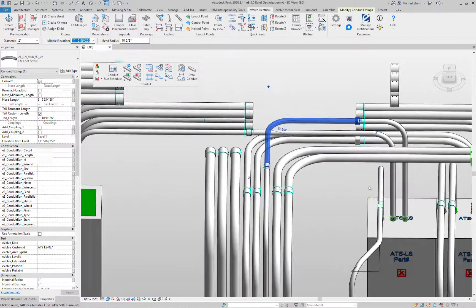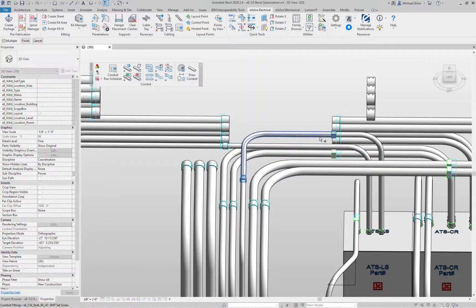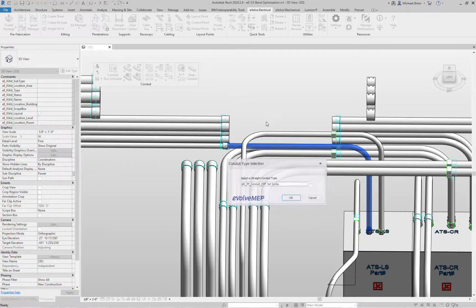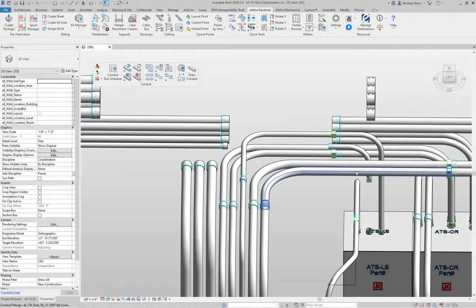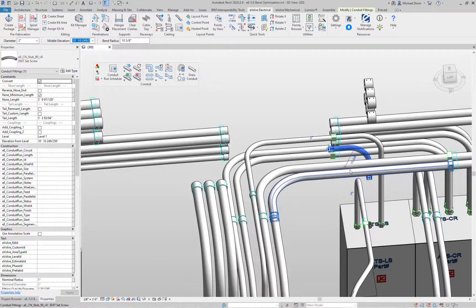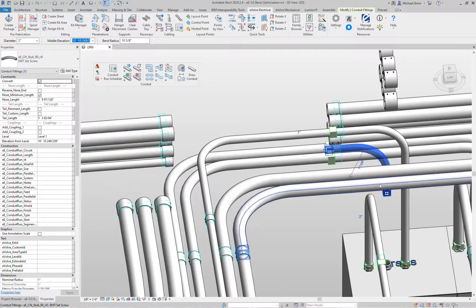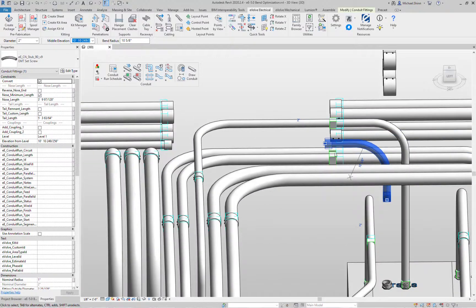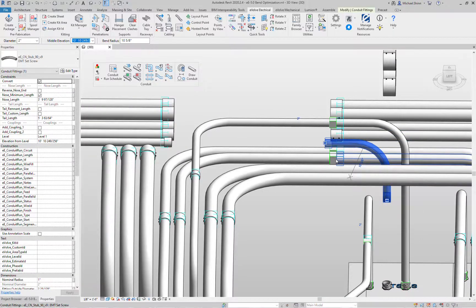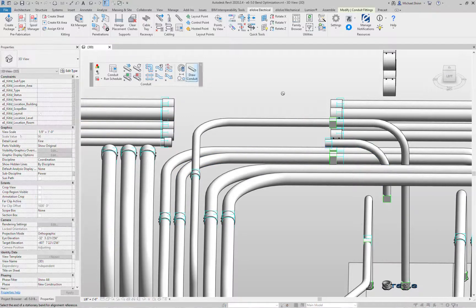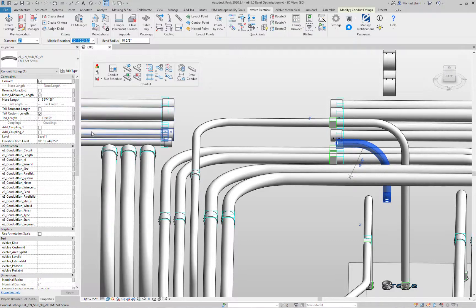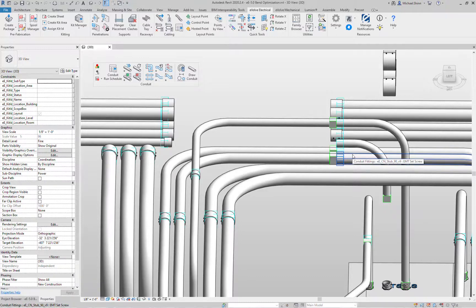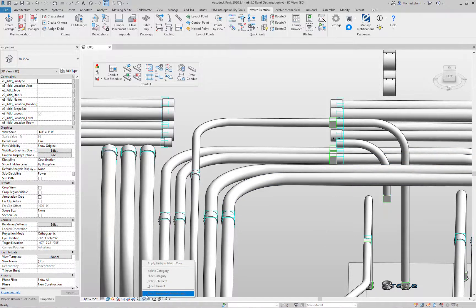There are tons of different controls as you rotate this around. Let me do a quick test — I'll reset this scenario. That now allows us to place couplings. What's great about these bent families is that resetting puts them back to minimum tail and nose length. Based on where this stub 90 is, it's at minimum nose length, which is off by a few inches from the other couplings. It's now up to you if you want to override those — note that by moving it back, it turns off the minimum nose length and shortens it up, but you're seeing exactly what you're looking for and it's giving you instant data back in your view.